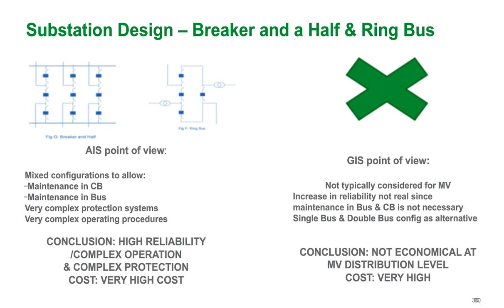A high voltage gas insulated switchgear configuration. So you can do it from an air insulated point of view, and because the switchgear is very flexible in that sense, where you can do a variety of bus bar configurations or a fully customizable bus bar arrangement, it is possible. However, with GIS, it's just typically not achievable from a cost perspective to the customer.